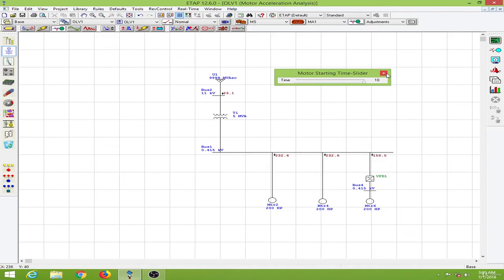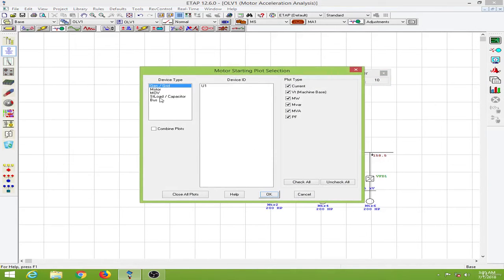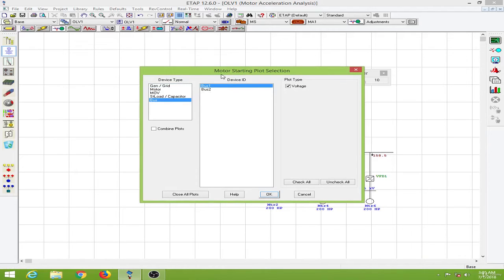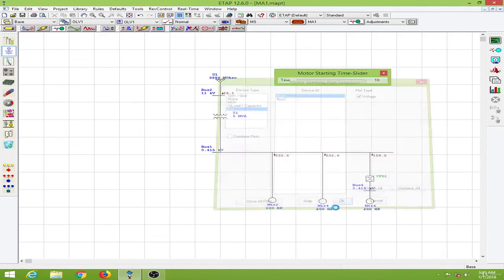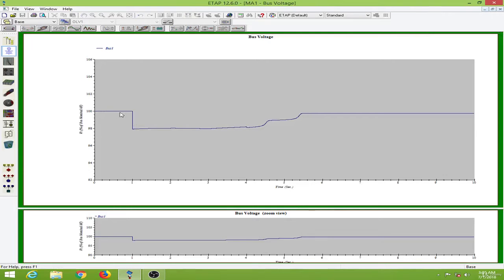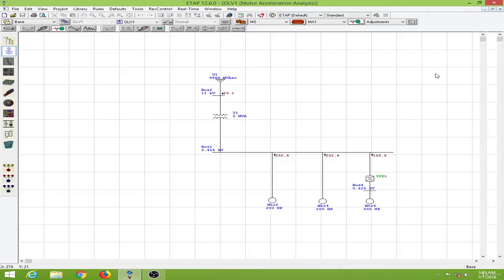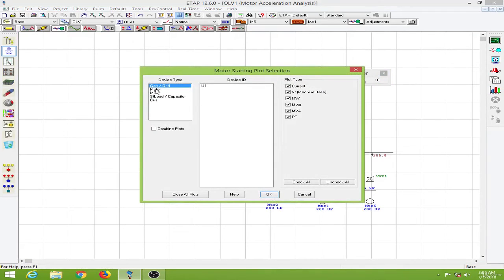Now let us observe the motor starting plots. First I will observe the bus voltage, so let me choose bus 1 and click OK. Because all motors are being started at the same instant we will have a significant drop in voltage — we have come down to 98 percent of the nominal voltage. Let me close this and observe the motor plots.